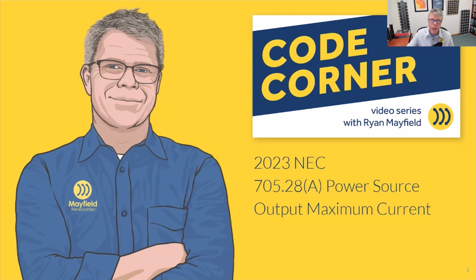So when you're doing that, you're going to be looking at Article 705 in general, and specifically 28(A), where we are looking at the output currents for our sources. This is similar to what folks who have been doing solar systems know from 690.8. This is akin to that, where we're defining maximum current values based on what type of circuit we have, what kind of equipment we have, how we're controlling it. So we'll jump into that.